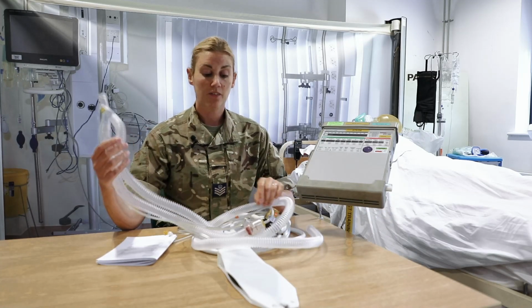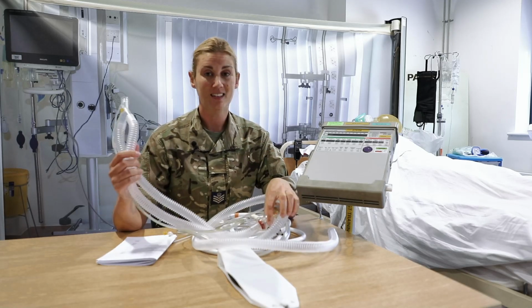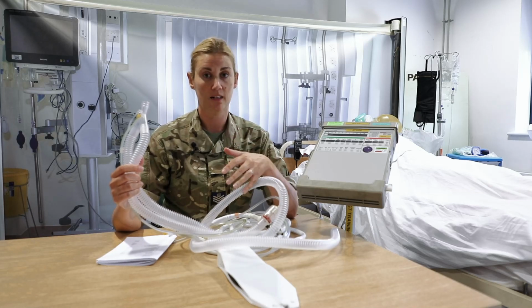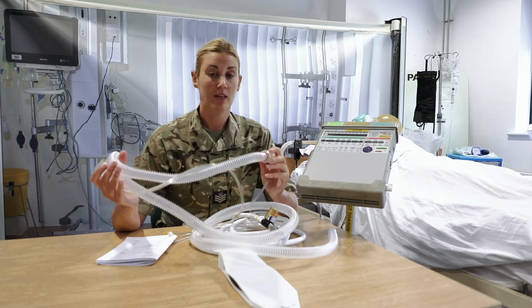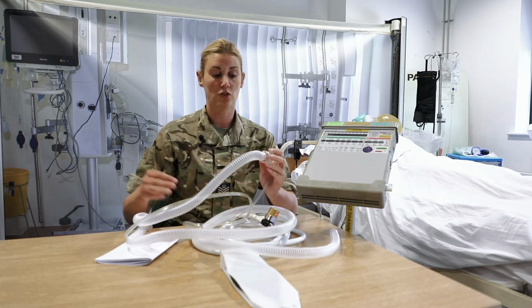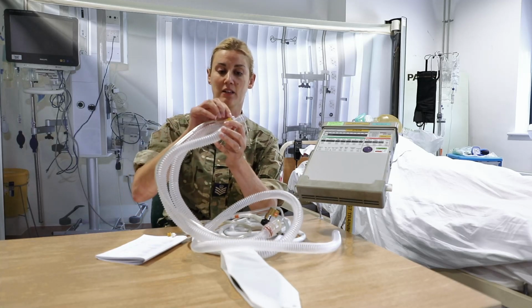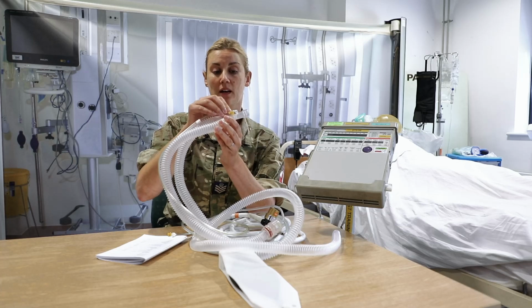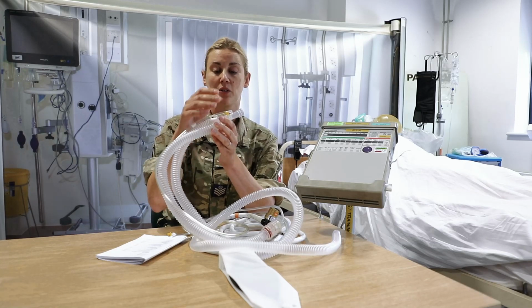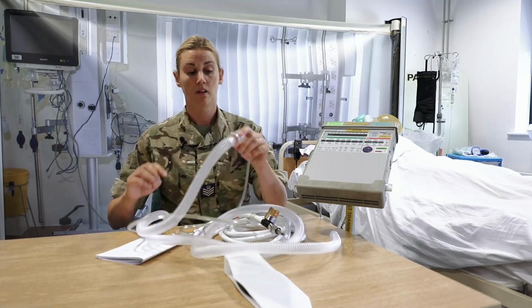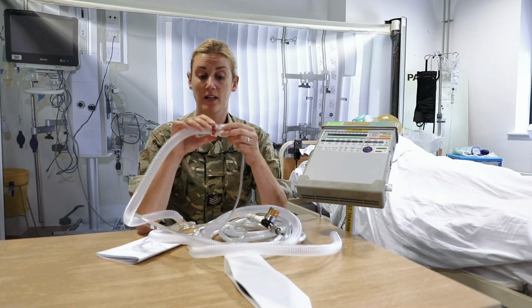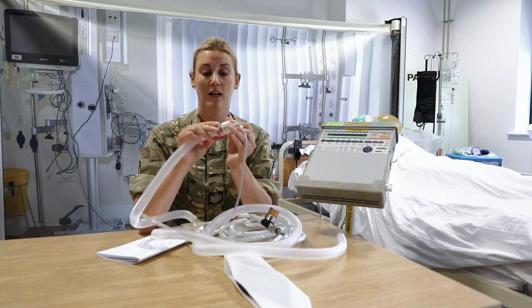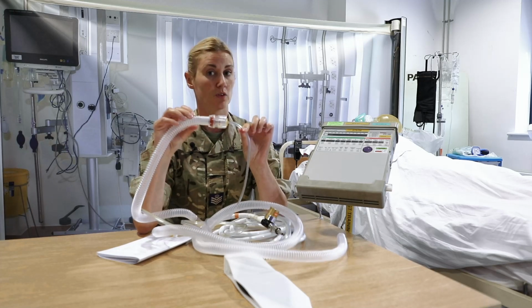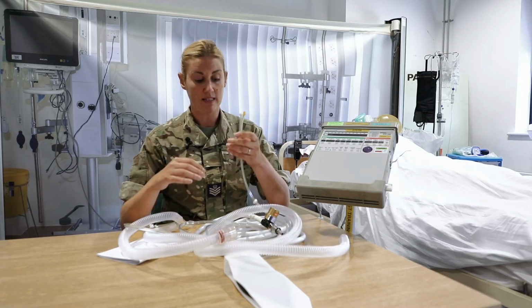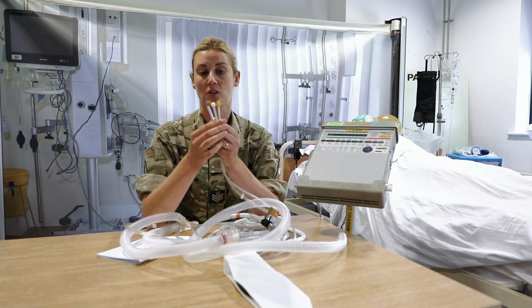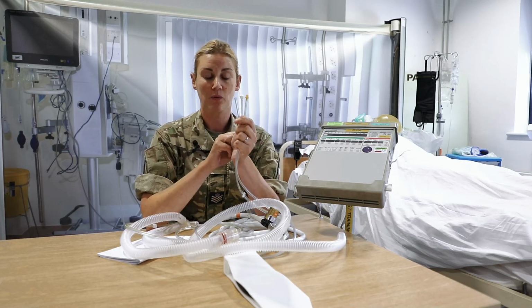It's good practice to give your ventilator circuit a quick once over. Now this is obviously a training circuit, and you will use training circuits for the routine checks of the piece of equipment. But if you get out a new circuit, there's a few things that we would recommend you check. First is the integrity of your right angle ports up here. It's quite brittle plastic, they can break very easily, so when you get it out of the packet, just confirm that nothing is broken. On the PEEP valve itself, have a good look inside, make sure that that spring is still intact, and just have a go at adjusting that PEEP setting, just to make sure that your valve is going to work. And finally, working your way down to your transducer ports, just make sure that you've got 3 of them. You should have a yellow, a white and a plain one, and make sure that they're all intact and good to go.